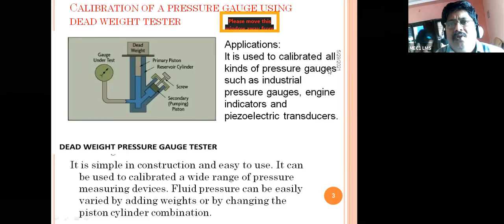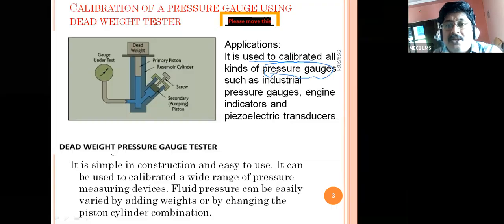Now let's look at the applications. It is used for calibrating all kinds of pressure gauges. With the help of this dead weight tester, we can calibrate all pressure gauges, to check whether each pressure gauge reading is correct or wrong.